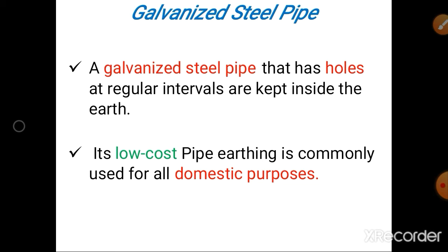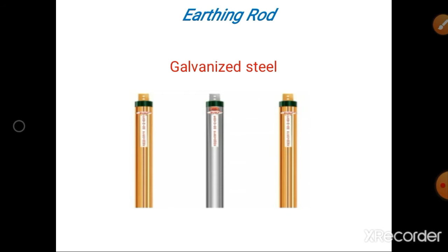The third one is rod earthing. Similar to pipe earthing, here instead of a galvanized iron pipe, we use a galvanized steel rod. This rod is also buried inside the earth at a depth not less than 3 meters, and this rod has low resistance, so it can easily ground the short circuit current. This is one of the advantages of rod earthing, and this is the galvanized steel rod used for rod earthing.